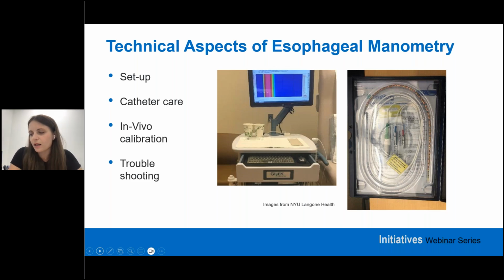If the catheter didn't calibrate despite all these points, you can try what's called a tune system on the Medtronic system. This basically provides a gentle reset of all the sensors in the calibration chamber. It takes a couple of minutes, so sometimes it can put you a little behind if you are trying to get another patient in the room. And if after that it's still not calibrating, calling technical support would be the next recommended step to further discuss troubleshooting and if the catheter does indeed need to be replaced.